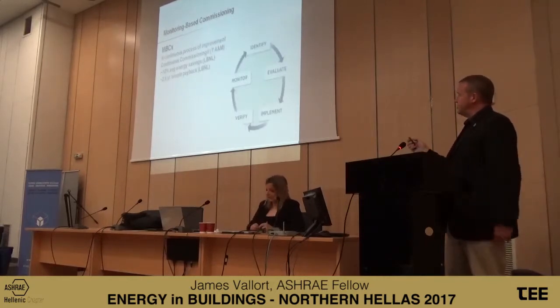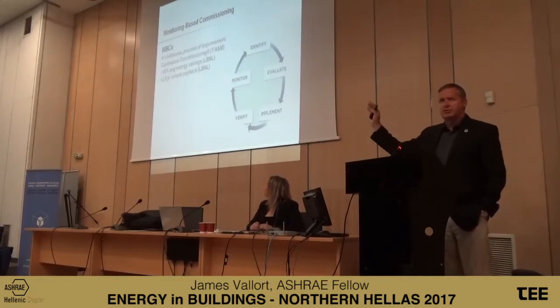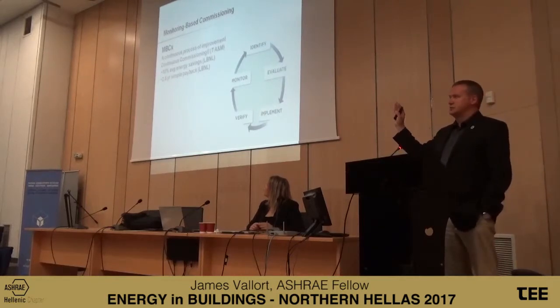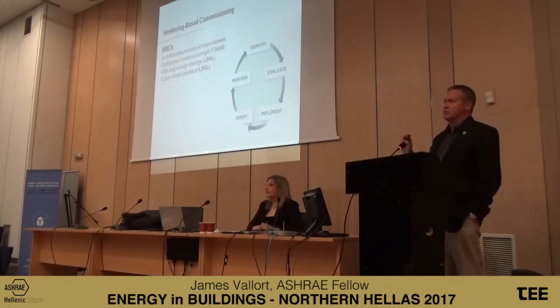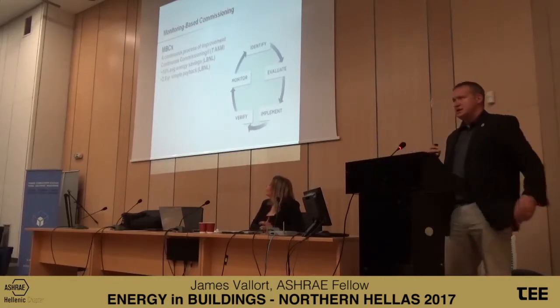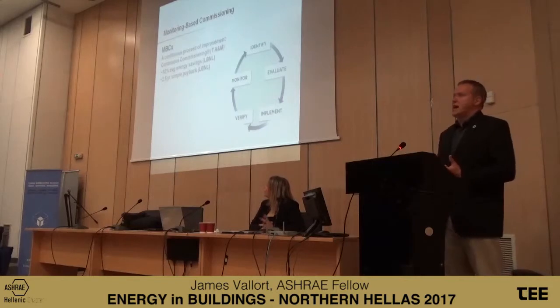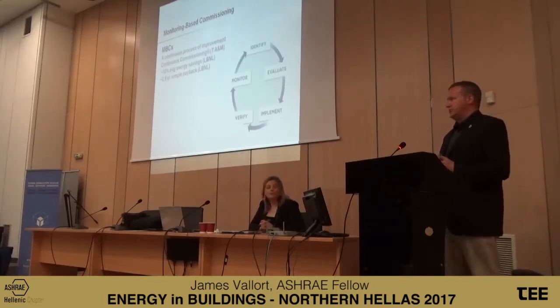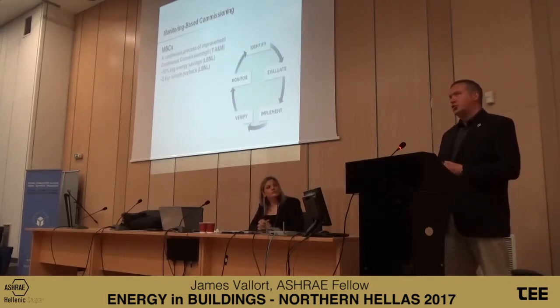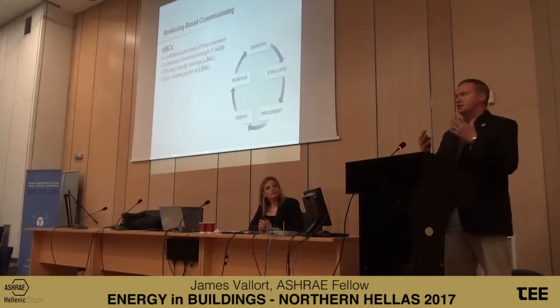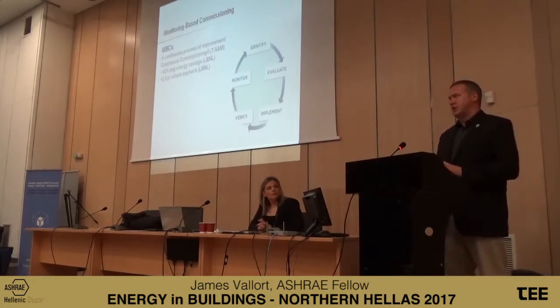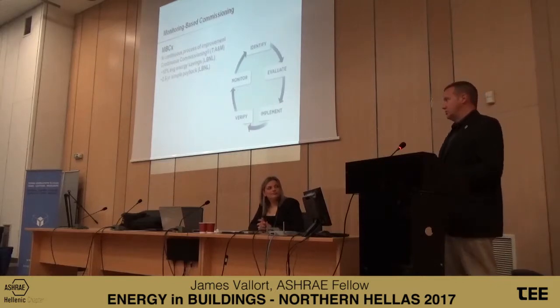That leads into monitoring-based commissioning. How many people have worked on or read white papers on monitoring-based commissioning? I think it's one of the newer trends we'll see because it goes hand in hand with big data. If you look at older systems, you had maybe 10, 20, 30 points for a central plant to monitor. Now you have maybe 10,000 points coming back from a central plant. How do you even know where to look?